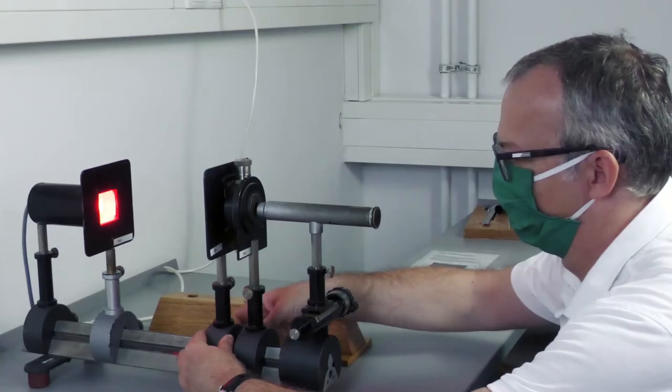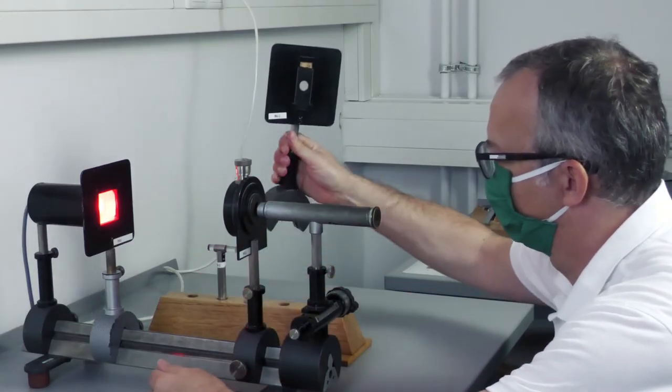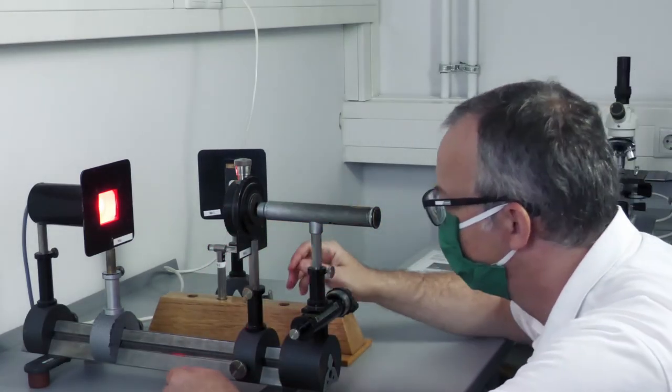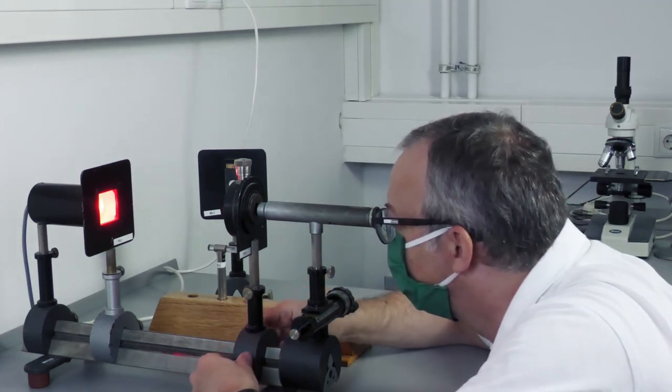To determine the aperture of the slit, the glass scale is now removed. First, the image of the slit is brought into focus by moving it. The gap width is measured with the micrometer drive under the tube.